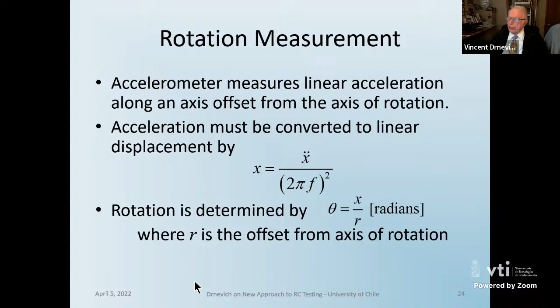Now, for rotation measurement, an accelerometer measures linear acceleration along the axis, which is offset from the axis of rotation. So the linear acceleration has to be converted to linear displacement, and you do that by integrating it twice. And for sinusoidal motion, that's simply divided by the circular frequency squared, or 2 pi times the frequency, squared. And then rotation is to take that displacement and divide it by the value r, where r is the offset from the axis of rotation. So now we have a measure of the rotation of the top of the specimen.